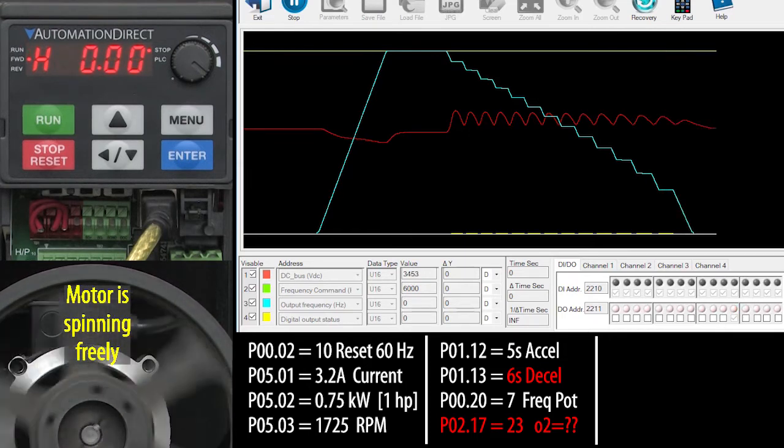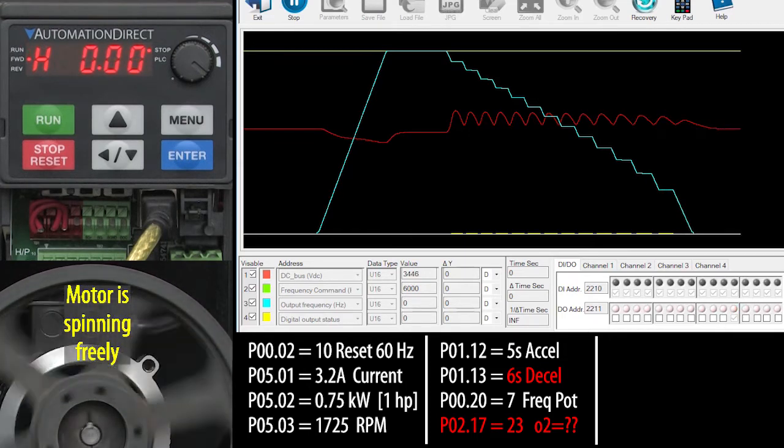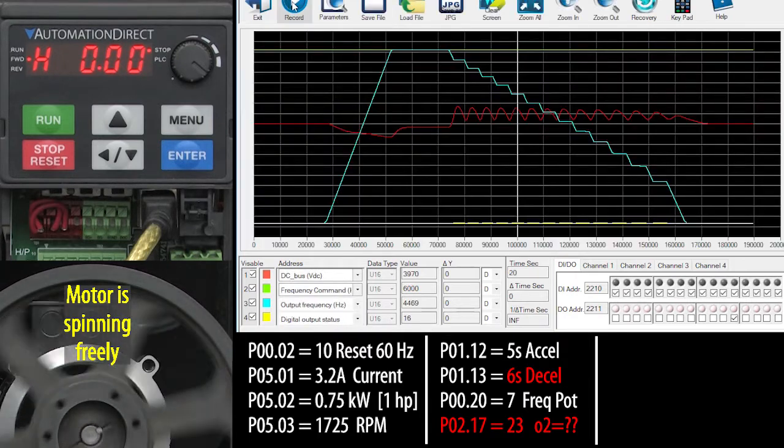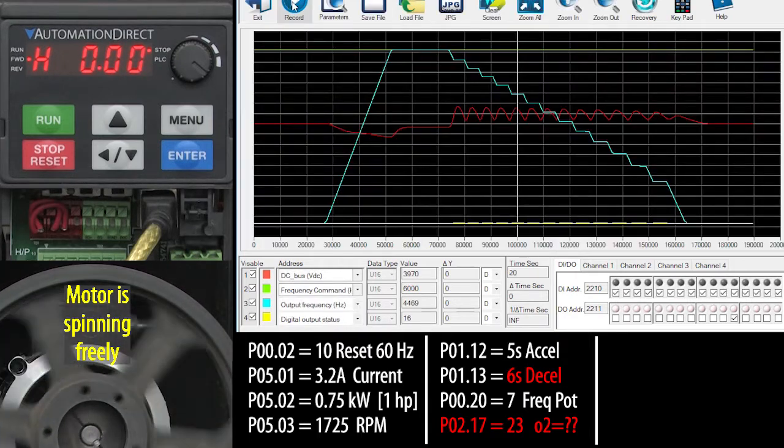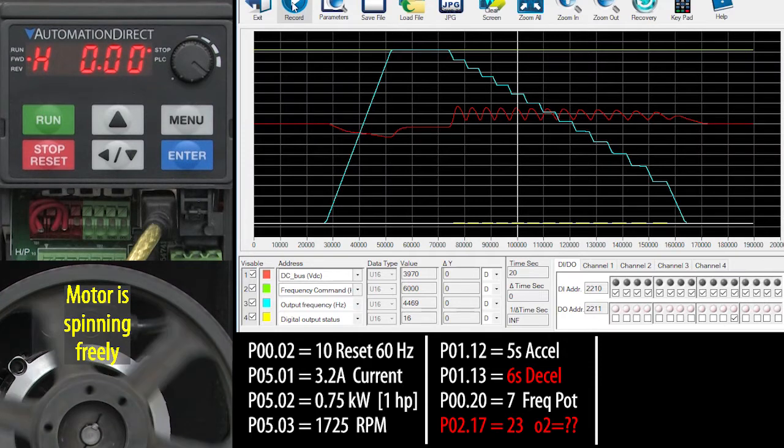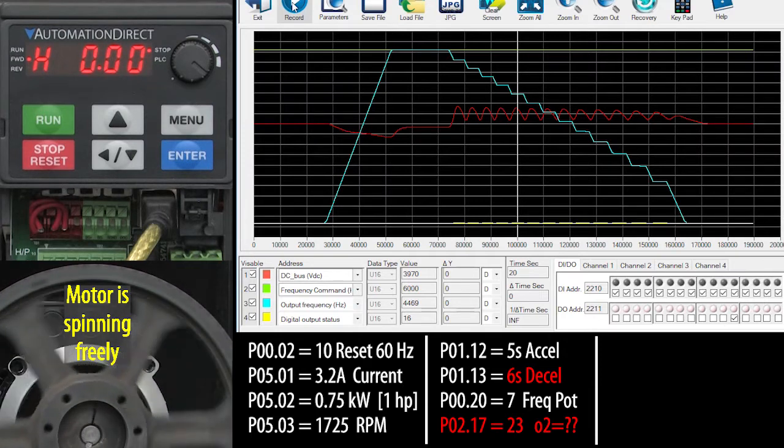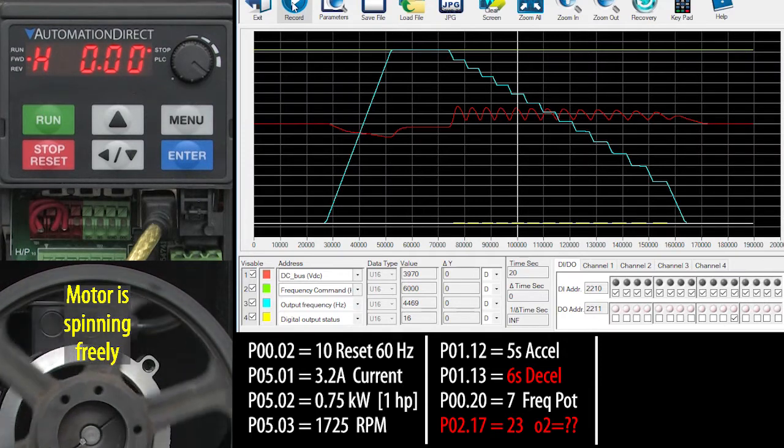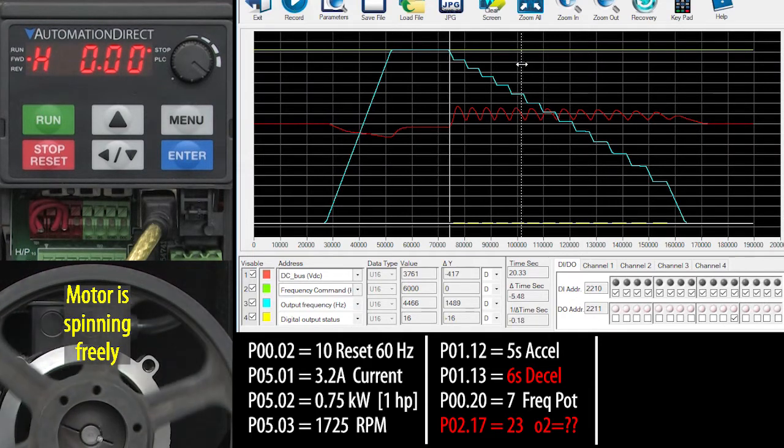Well, let me stop the scope and zoom in. Ok, here's the deal. What you are seeing is the drive automatically slowing the ramp down to keep the DC bus from rising too far.